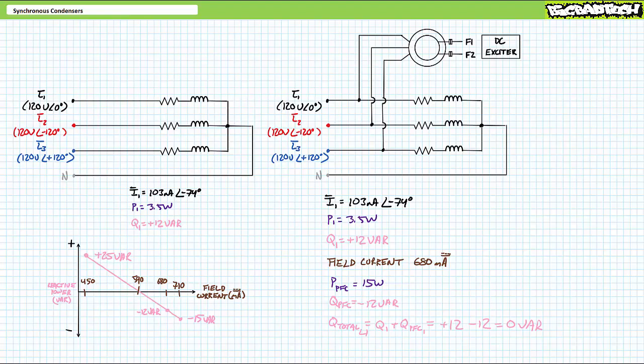When we bring the synchronous condenser in parallel to the load, each load continues to consume positive 12 VARs of reactive power as previously. When we increase field current to approximately 680 mA DC and slightly over-excite the rotor, each winding of the synchronous condenser consumes roughly 15 watts of real power for friction, yet supplies roughly negative 12 VARs of reactive power — equal in magnitude and of opposite polarity to the load. Given current to the load lags and current to the synchronous condenser leads, source current (the summation of load and synchronous condenser current) appears in phase with supply voltage. The equal and opposite reactive powers cancel such that each phase only needs to supply 3.5 watts to the load and 15 watts to the synchronous condenser, for a total of 18.5 watts. Any reactive power is exchanged between the load and the synchronous condenser at the point of use, and the source stays out of it.